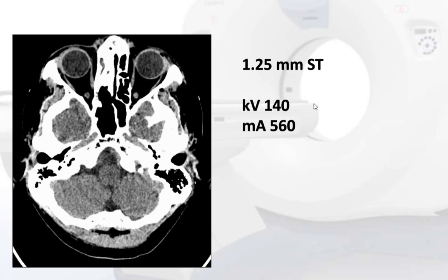For a head CT, the KV is the same throughout the scan — they use higher KV of 140 for head. KV will not change during the scan no matter where they are scanning. For example, in this scan the MA was 560 for 1.25 millimeter slice thickness.